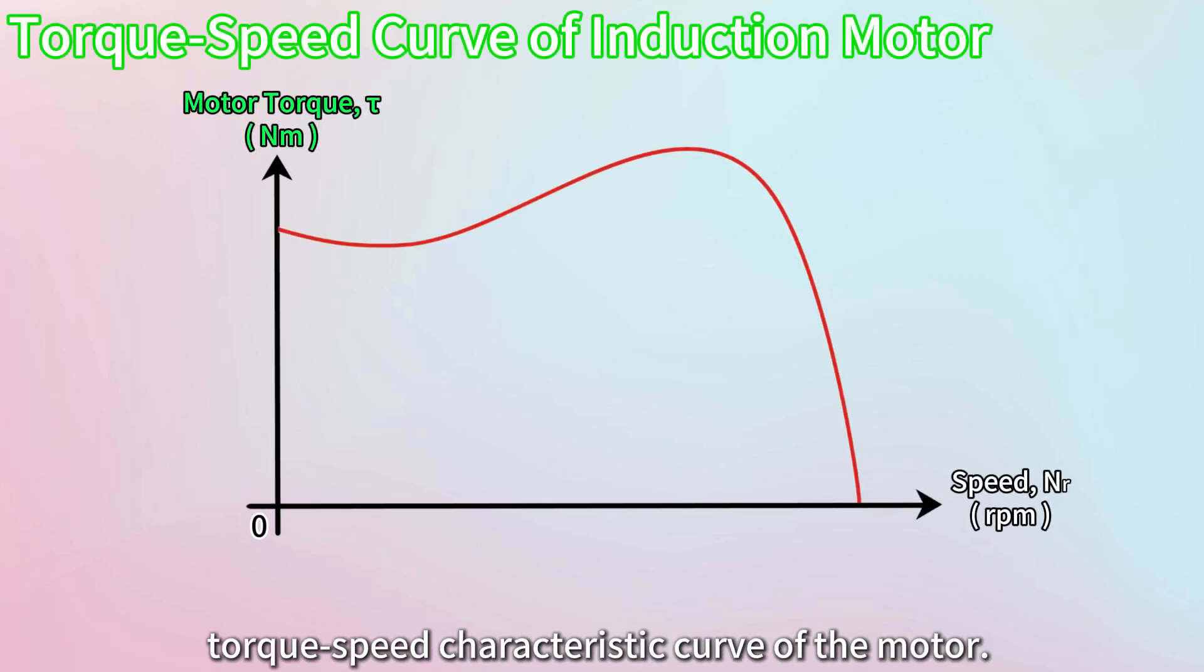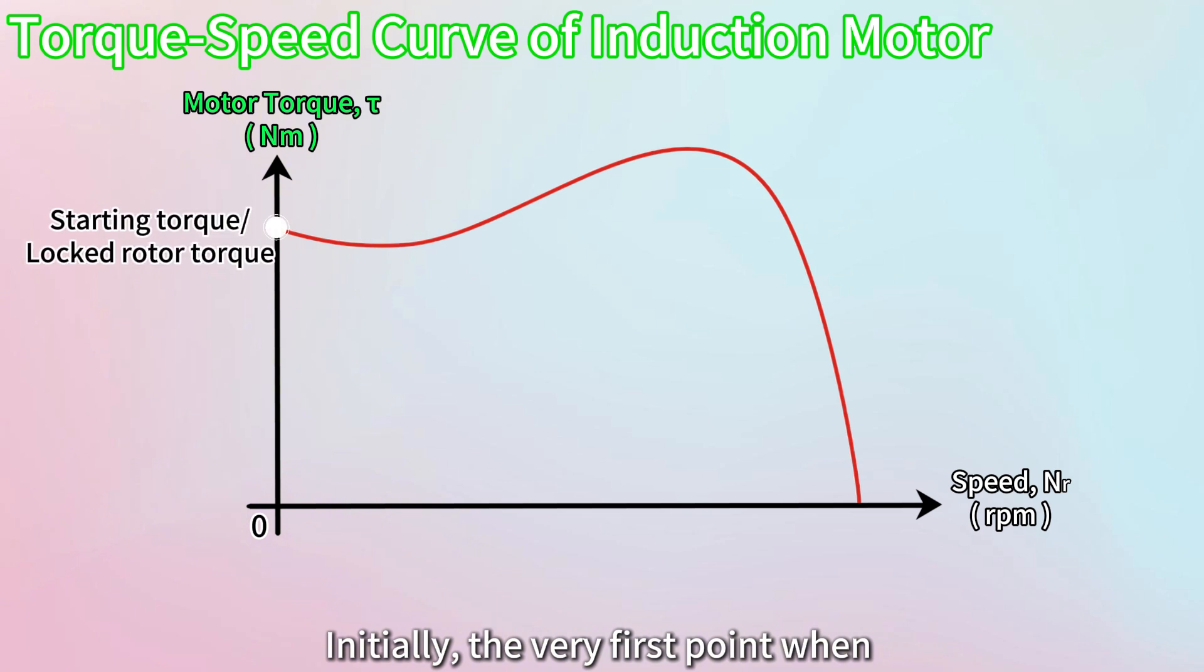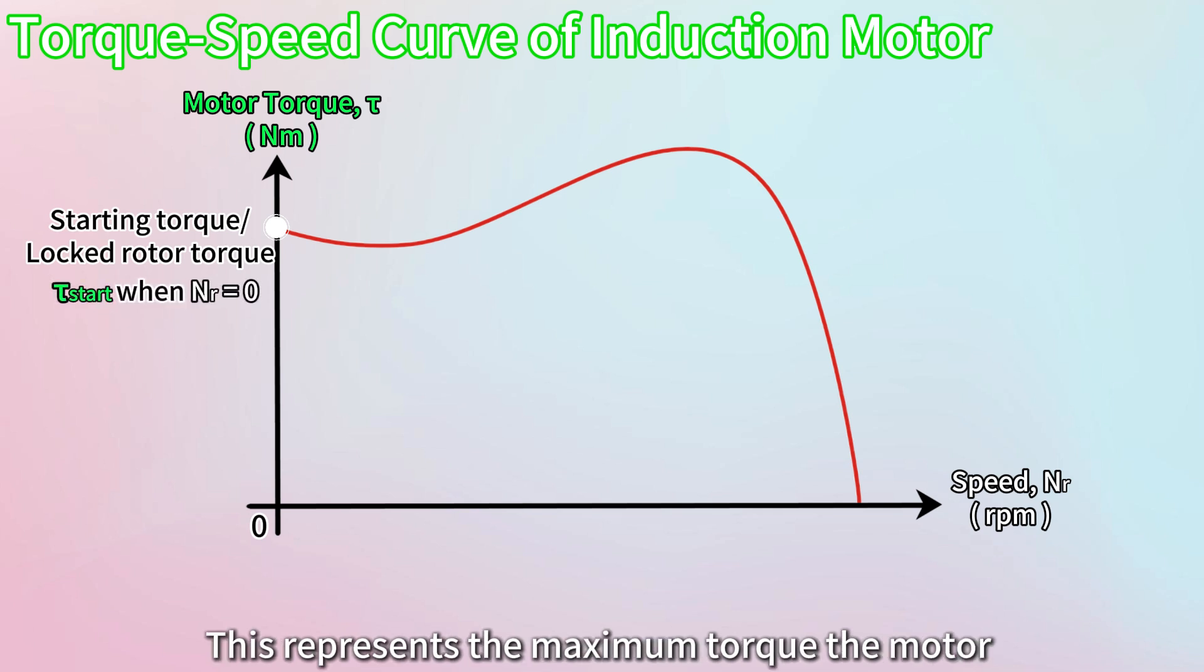Now, let's talk about the torque speed characteristic curve of the motor. Initially, the very first point when the motor starts to turn is known as the starting torque or locked rotor torque. This represents the maximum torque the motor can produce when the rotor is at rest or zero speed. As long as the load on the motor is less than or equal to this starting torque, the motor will successfully start.